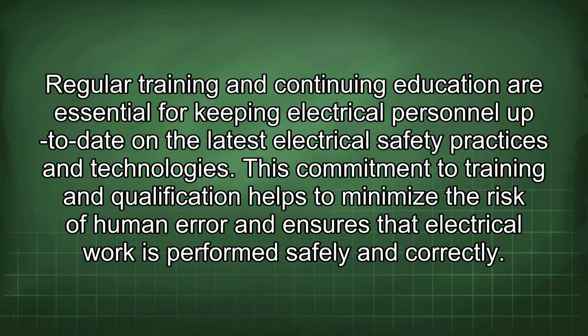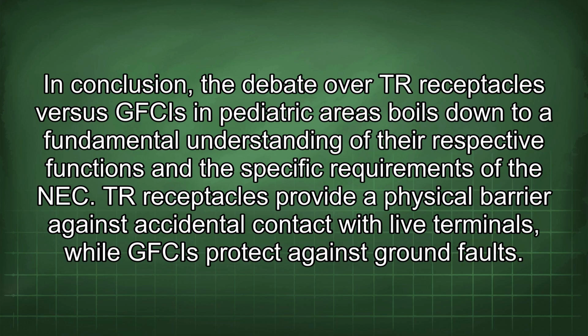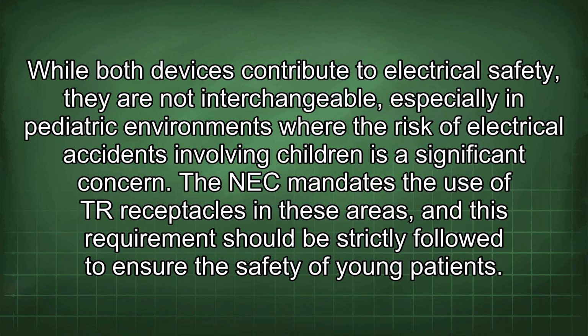performed safely and correctly. In conclusion, the debate over TR receptacles versus GFCIs in pediatric areas boils down to our fundamental understanding of their respective functions and the specific requirements of the NEC. TR receptacles provide a physical barrier against accidental contact with live terminals, while GFCIs protect against ground faults. While both devices contribute to electrical safety, they are not interchangeable, especially in pediatric environments where the risk of electrical accidents involving children is a significant concern. The NEC mandates the use of TR receptacles in these areas, and this requirement should be strictly followed to ensure the safety of young patients.